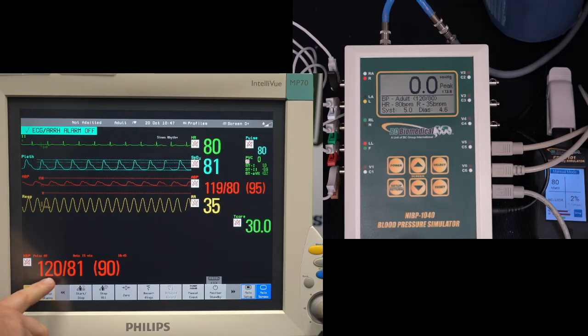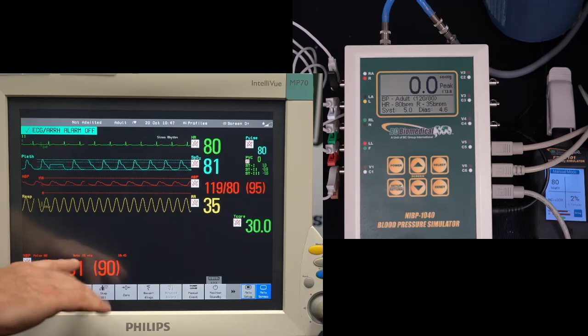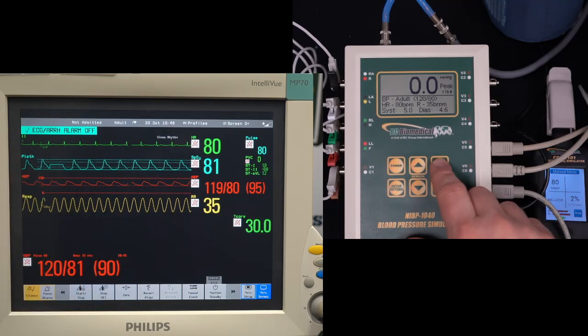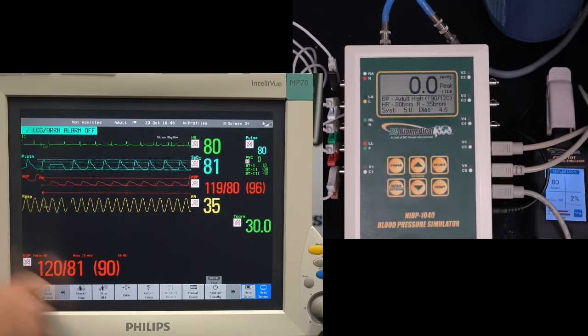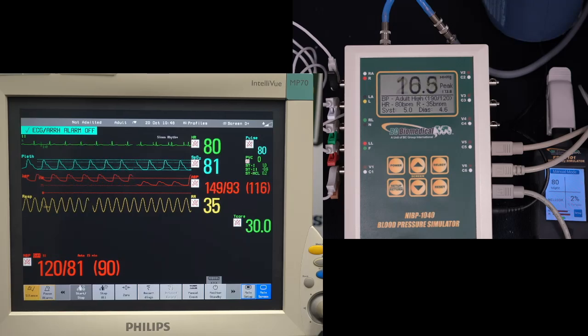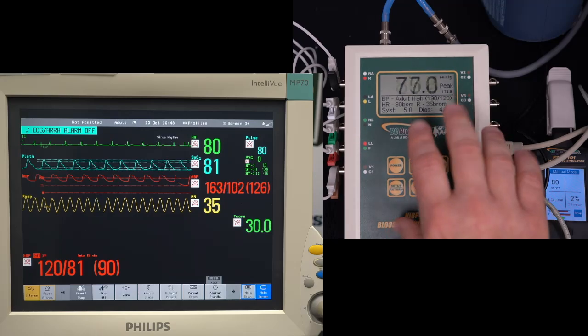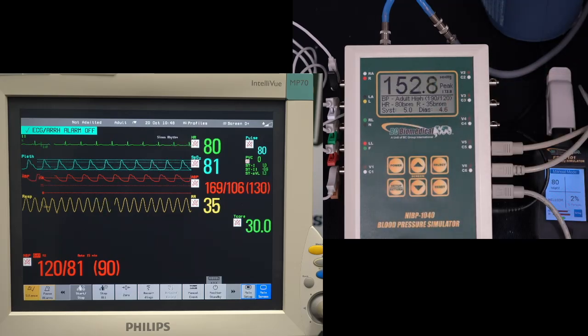I demonstrated the NIBP measurement. Right now it's on a 15-minute window. If we wanted to do adult high, we could just go in here. Now we could do a high and run that again. And it will automatically adjust, and the simulator is going to put out a simulation of 190 over 120 as selected in the screen here. And then we'll get that measurement on the monitor.